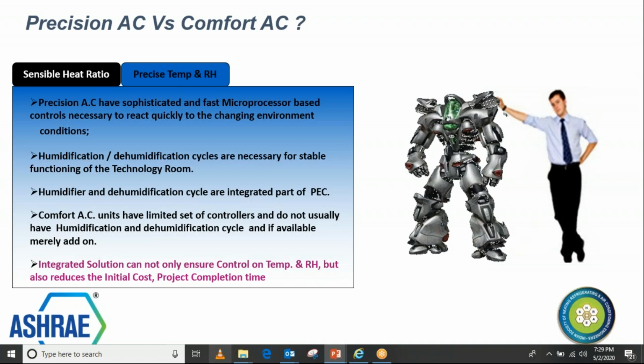Even at home, when you open your computer from the backside, or even your TV after a long time, you will see a lot of dust accumulated. But we never see it with our eyes flowing around the room, because the particle size of this dust is very small. In the precision AC concept, the filtration is up to 95% down to 5 micron, and in comfort air conditioning the filtration could be around 80% efficiency at 20 microns. So there is a difference in the design approach of these two air conditioning systems altogether.